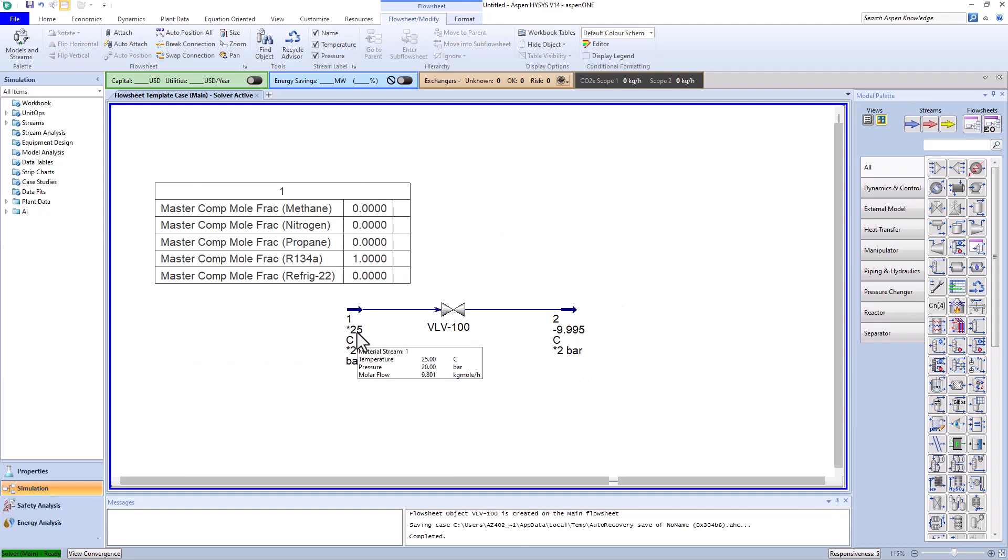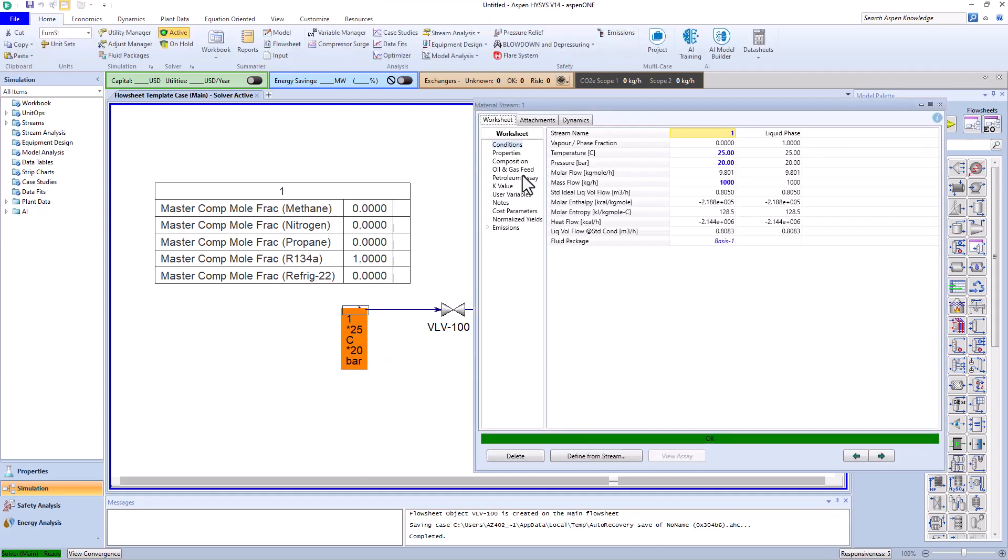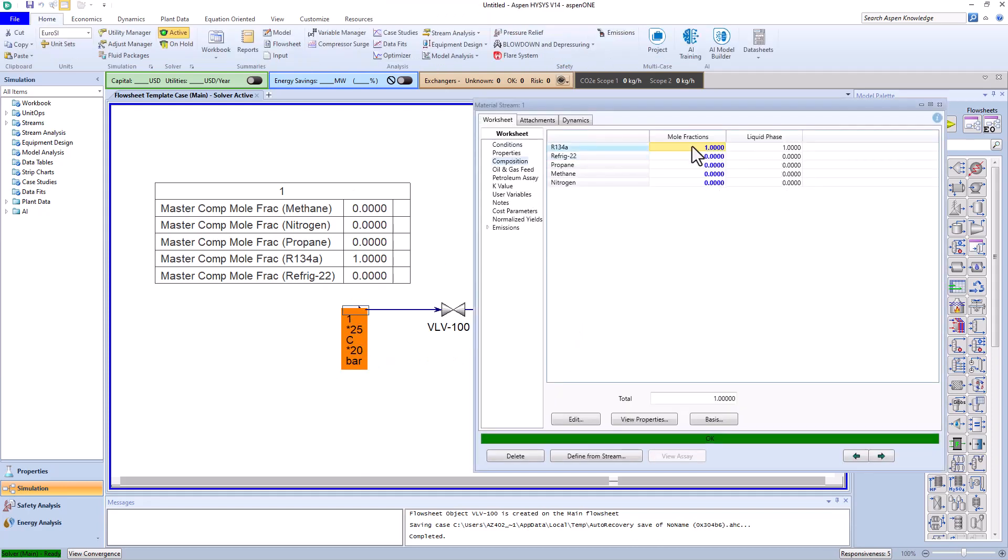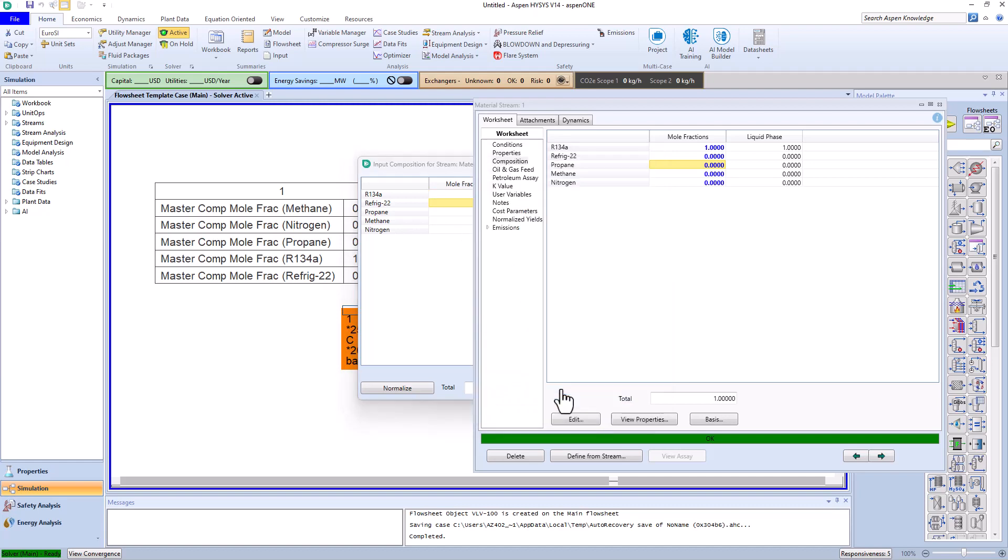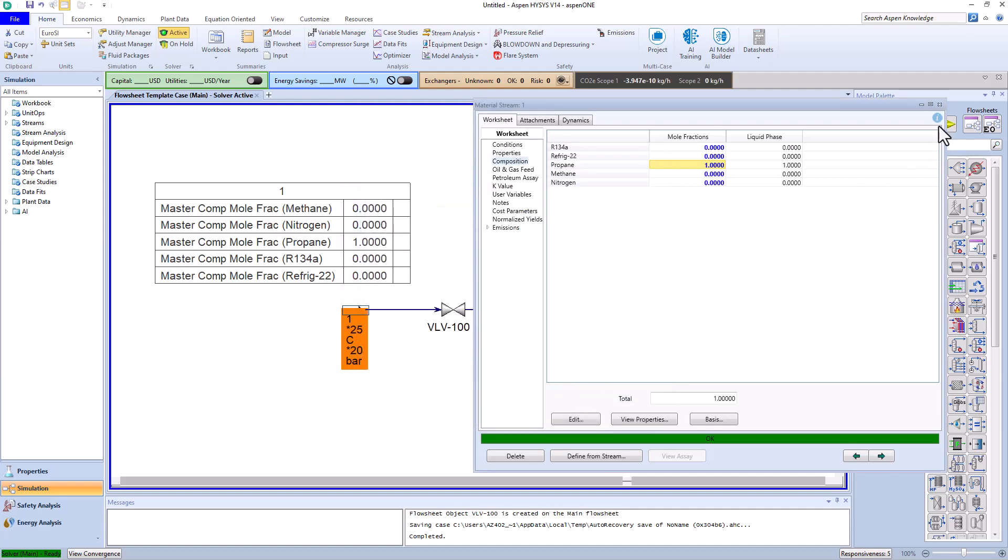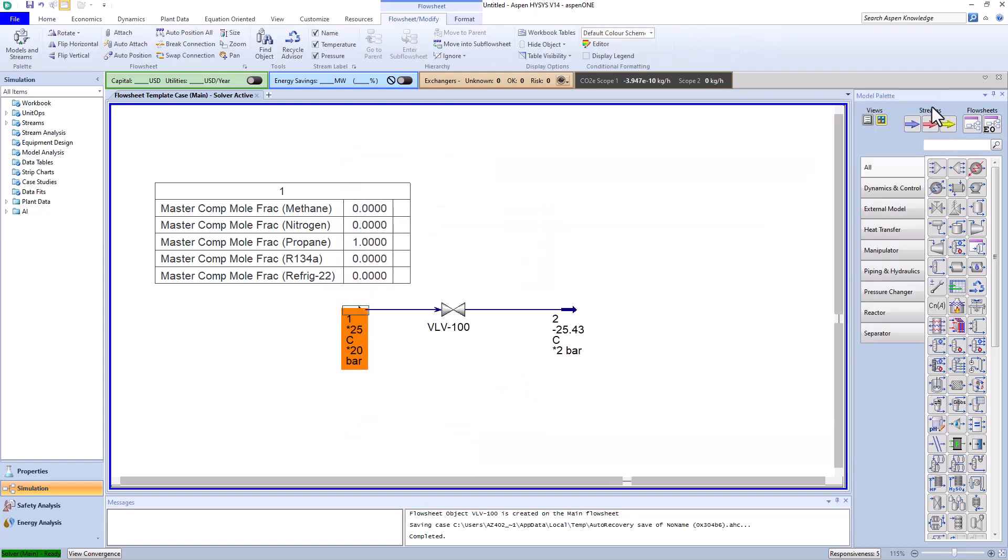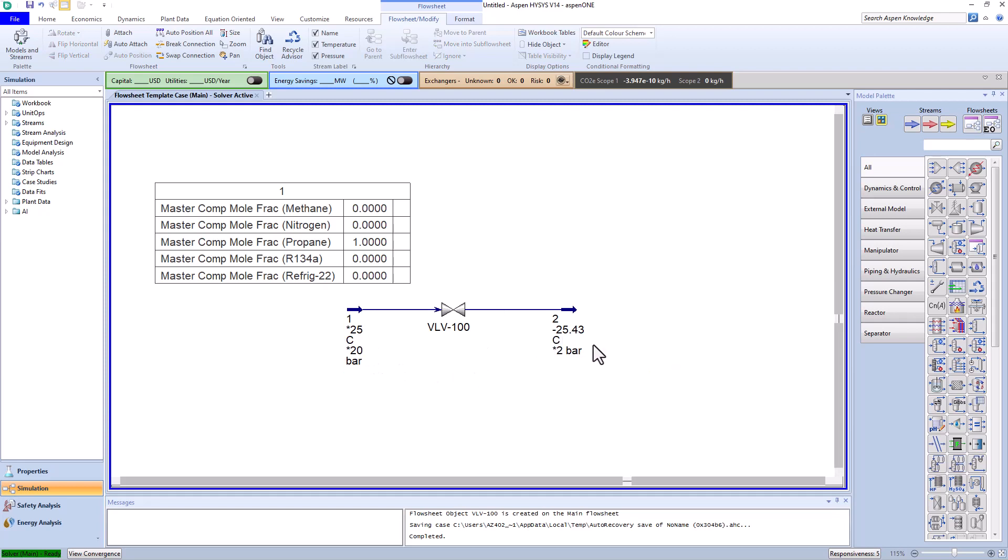Now here, instead of R134a, we set the propane mole fraction to 1 and consider the remaining mole fractions as 0. With this action, it's observed that the temperature is further cooled, reaching about minus 25 degrees Celsius.